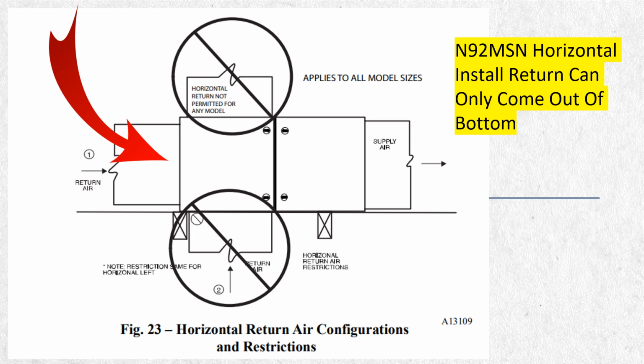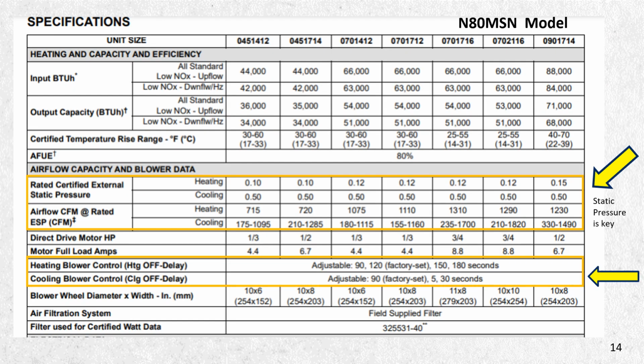The other thing too is when you're laying this unit down, horizontal left or horizontal right, you cannot use those cut-in tabs on the side. It will not get enough airflow. You have to come through the bottom of that. So keep that also in mind. And I've seen a lot of them do this, and they put an RBU box and then put your tabs coming out of the side. That's fine as long as the air passes through the bottom of the furnace.